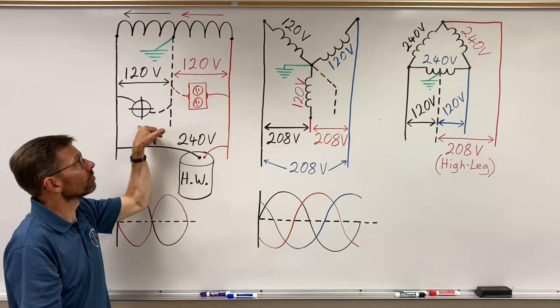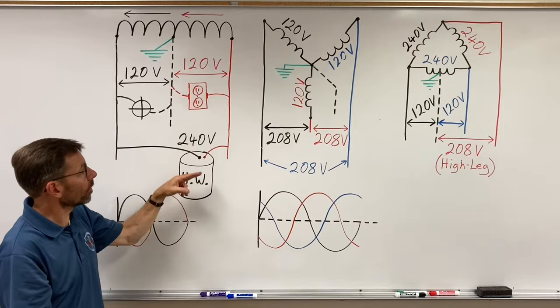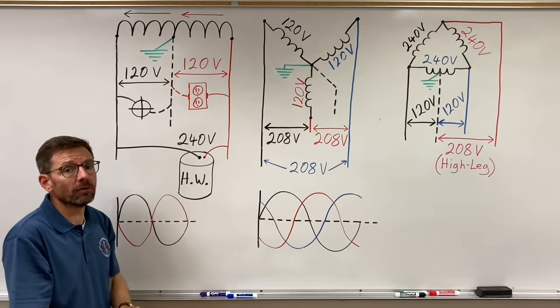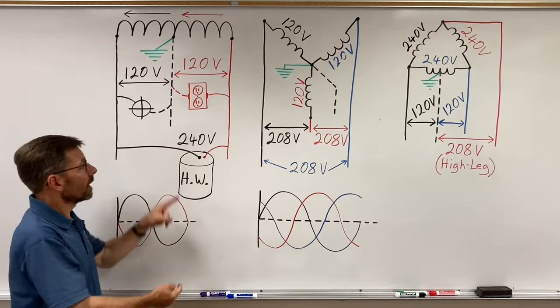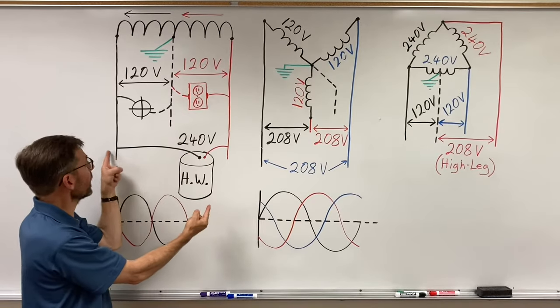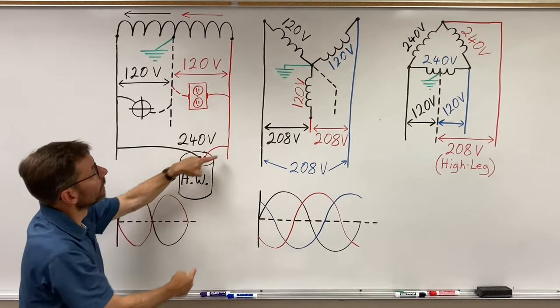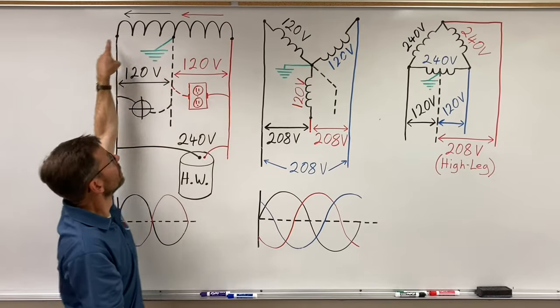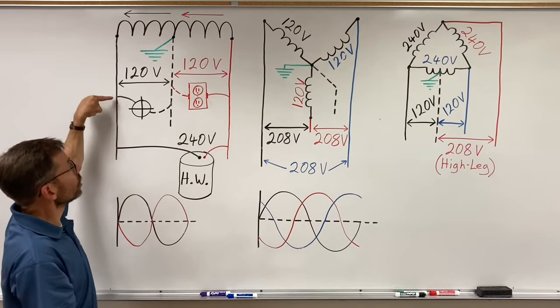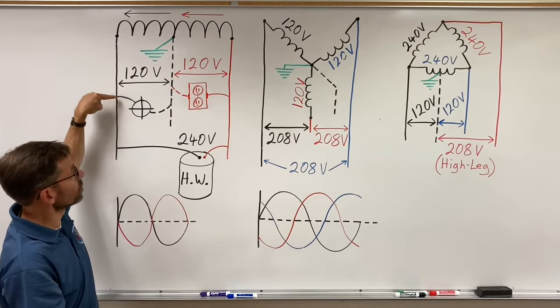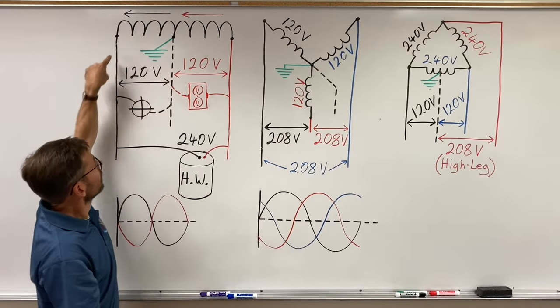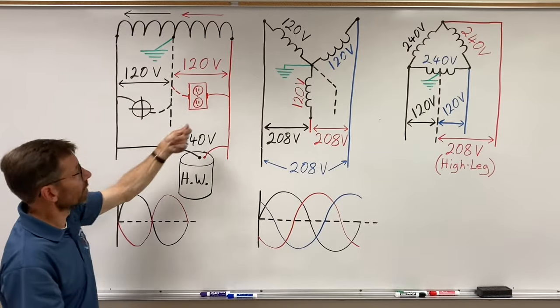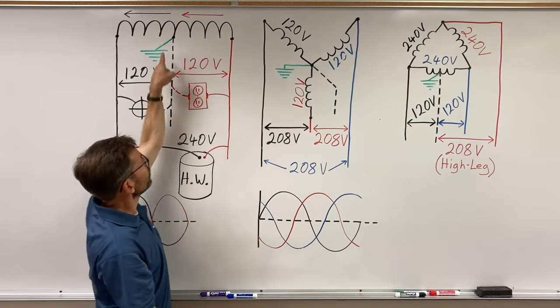We run our receptacles and lights off of 120 volts, and hot water heaters, baseboard heaters, and certain loads on 240 volts. For 240, I don't need a neutral — I just need a black and a red because the current just goes through the transformer. I use the neutral when I'm using a 120-volt load; when I turn a light on, it flows this way, or when I plug something into a receptacle, it flows this way.